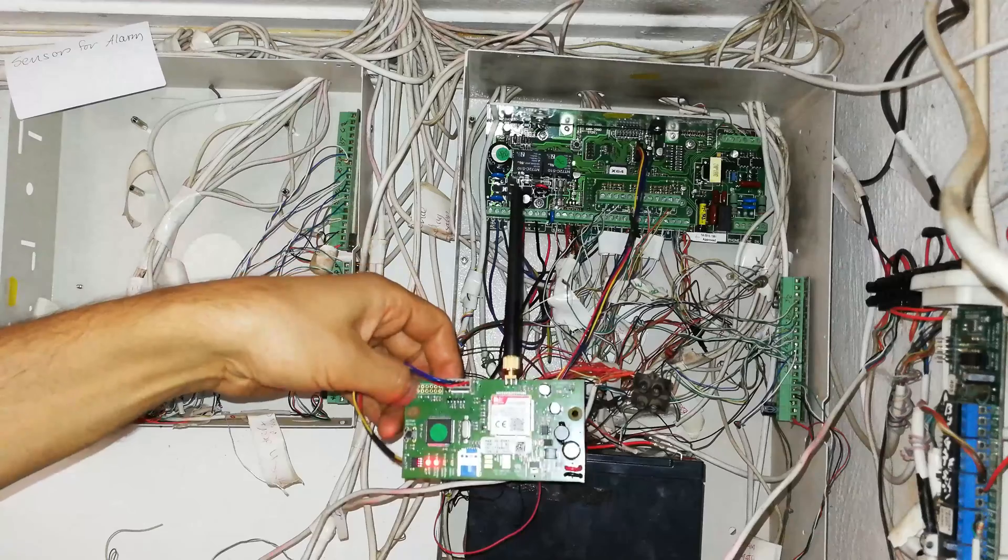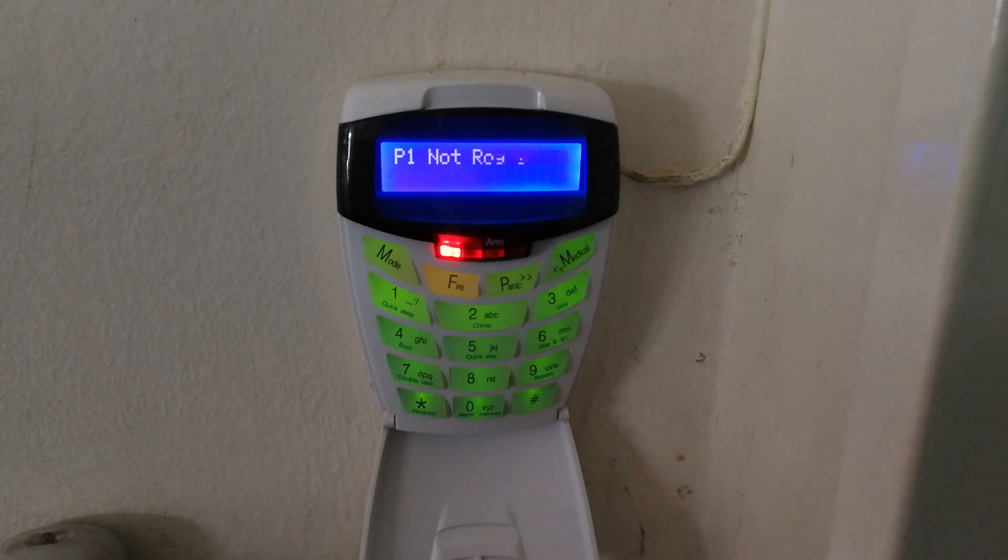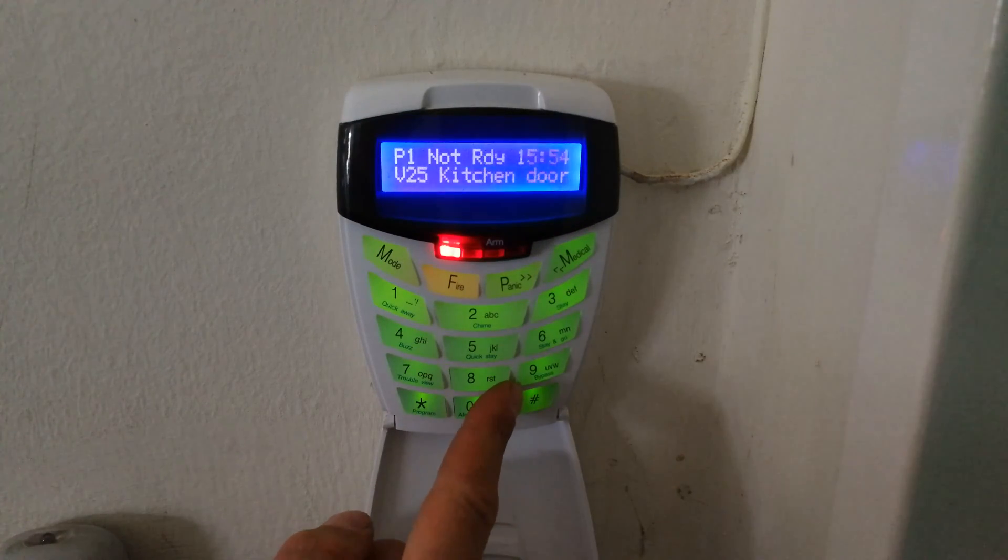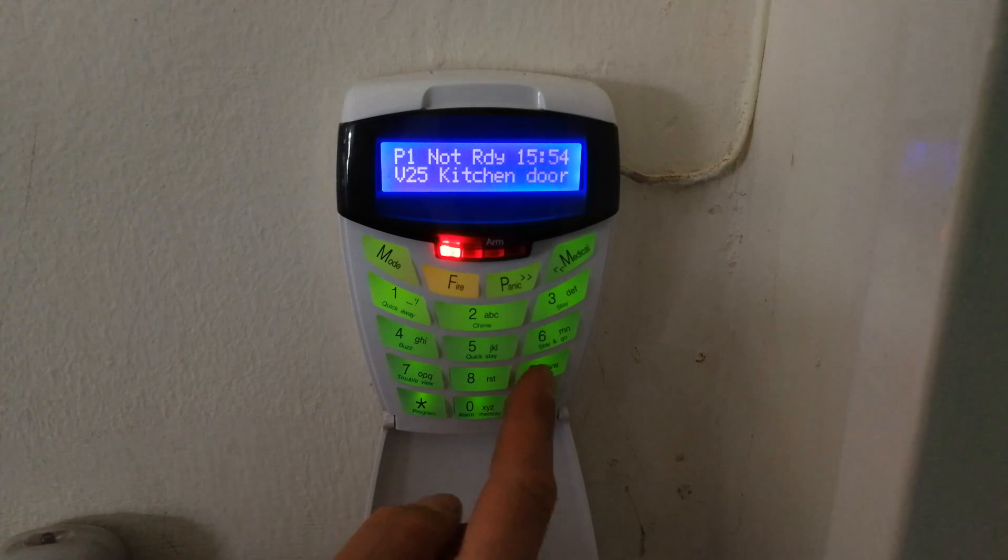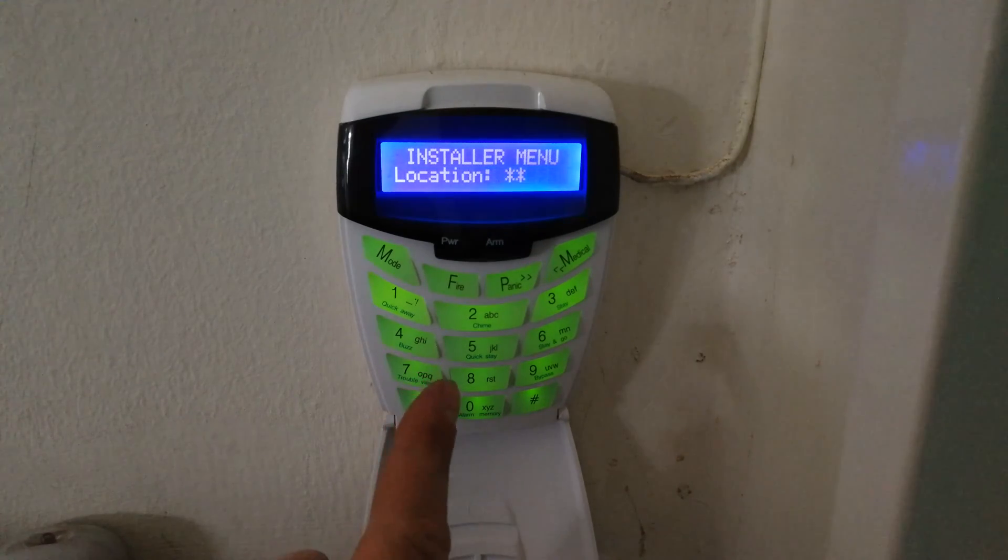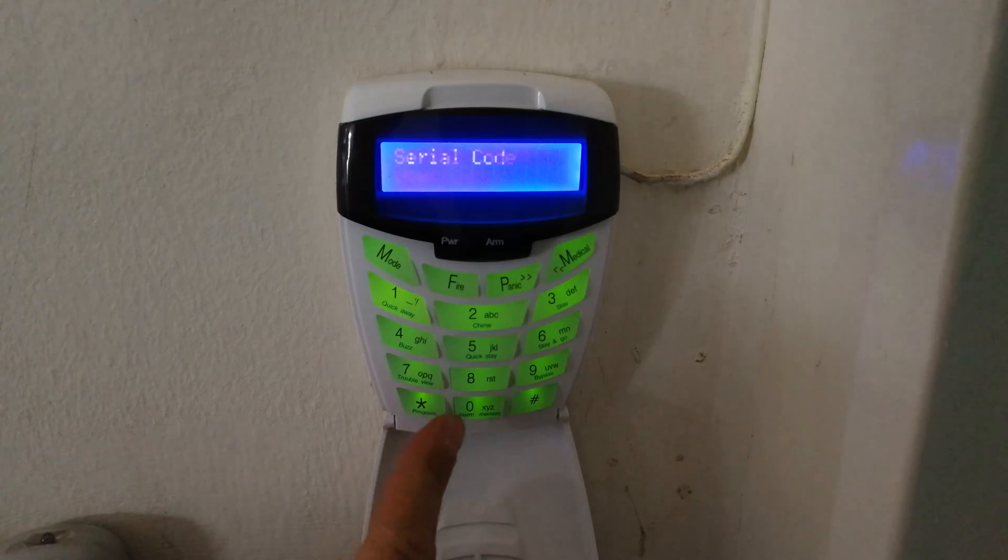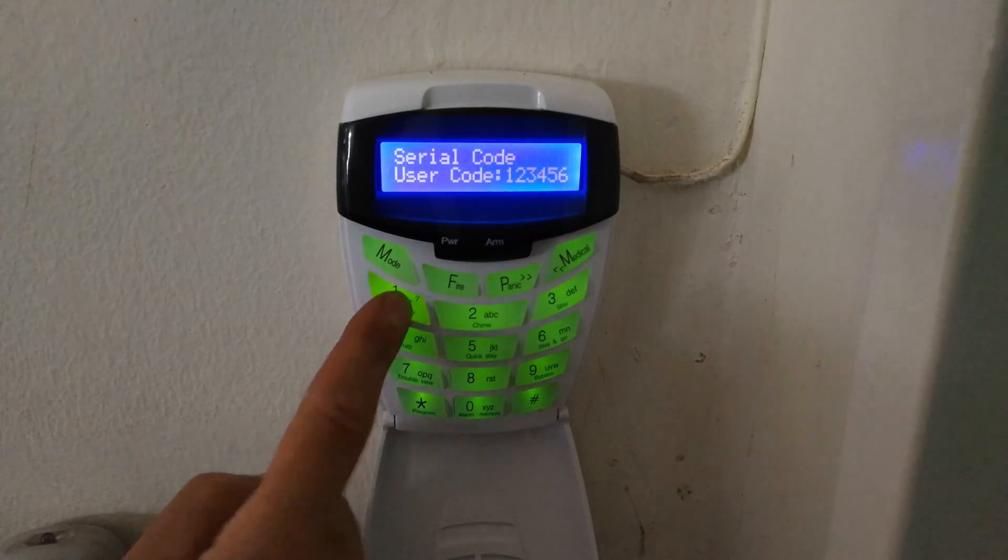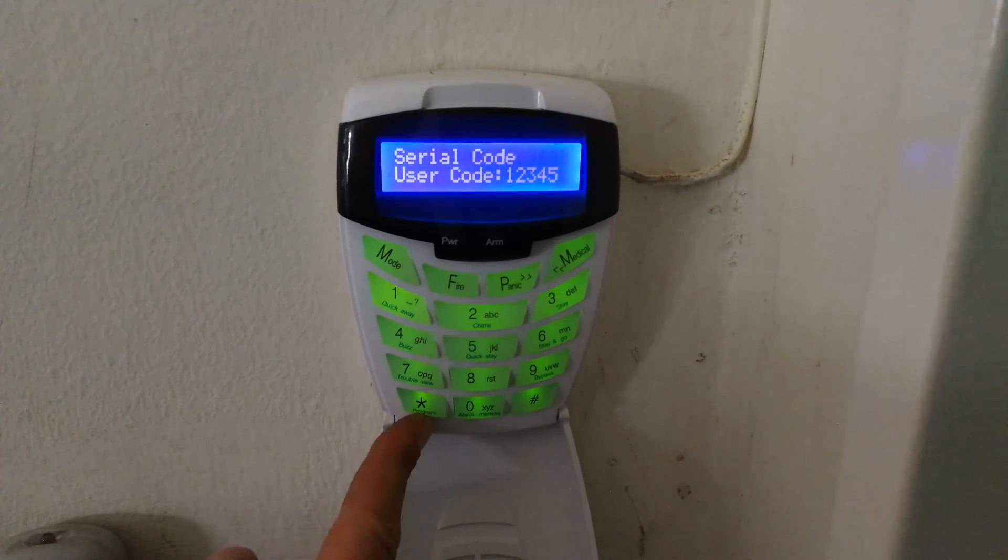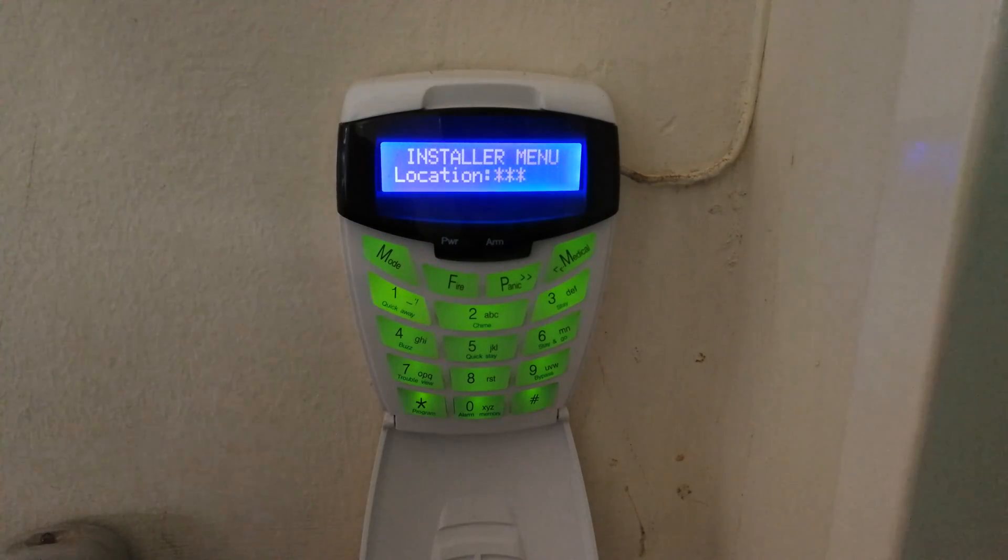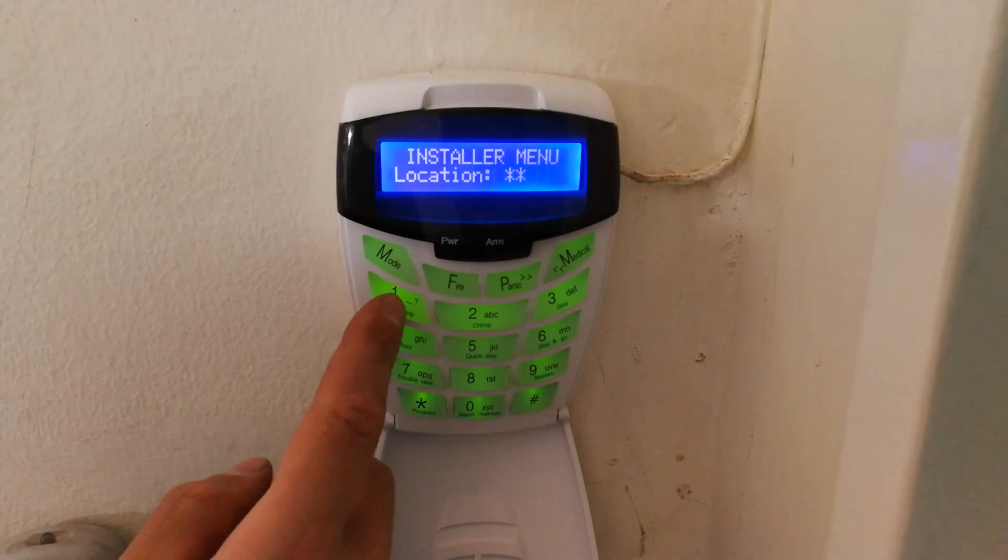After you've set it up on the panel, you need to come and quickly do an entry here. It's four nines—one, two, three, four—to get to the installer. Now you've got to go to location 196. Even though it says there one, two, three, four, five, six, you've got to still do one, two, three, four, five, six because you're resetting the link between the communicator and the panel.